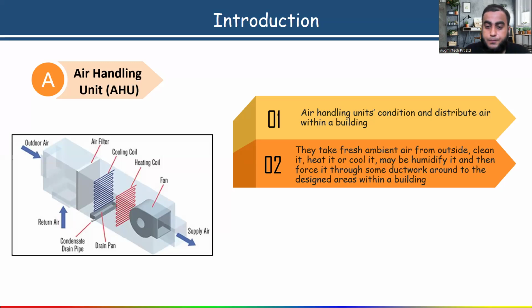Actually, remember for what location you are designing. For example, if I take the example of Hyderabad city, which is in India. When you check the relative humidity of that city, from the ASHRAE handbook you will get the outside design data in detail for each and every location. From there, the relative humidity of Hyderabad is around 28%. So we know that as per ASHRAE, how much humidity level do we have to maintain? Anyone? Relative humidity inside the room for human comfort. For human comfort as per ASHRAE, we always have to maintain the relative humidity between 50 to 55%.